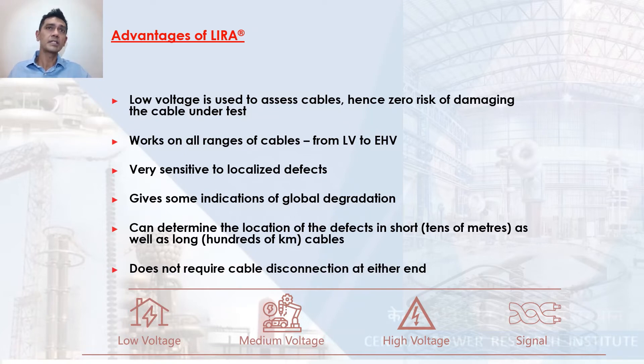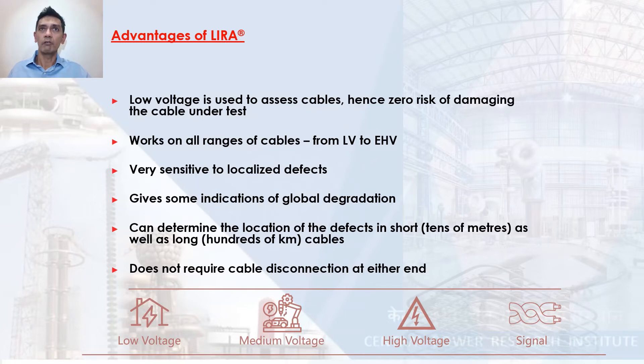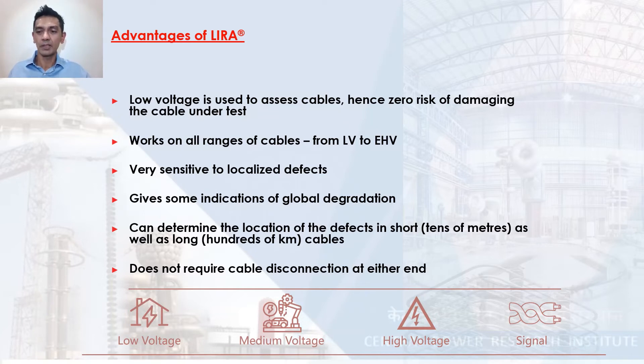Last but not least, Lira technology can be used without having to disconnect the cable, which is a massive advantage when you have a very short outage window and cables connected to GIS. In such a case, the disconnection and reconnection activity can be very time consuming and create new problems, so we can skip all of that.